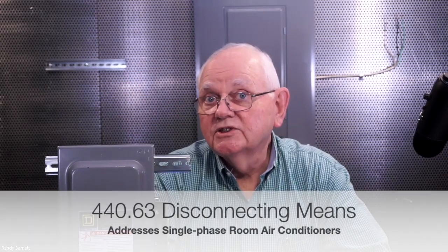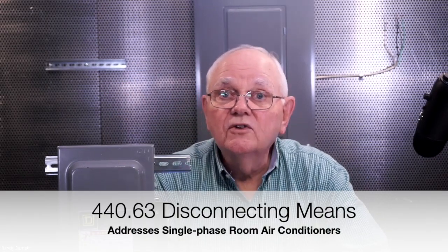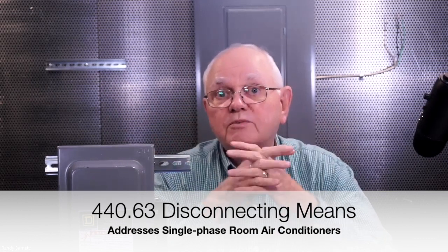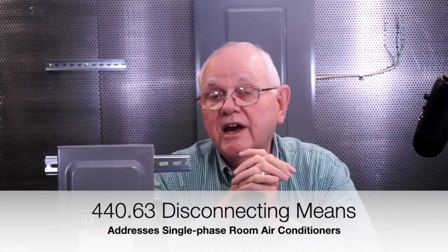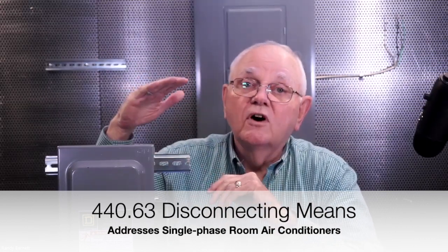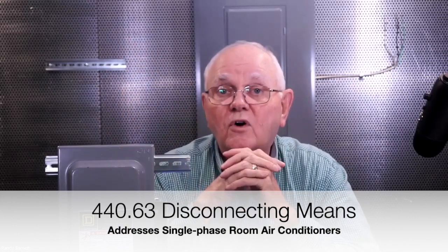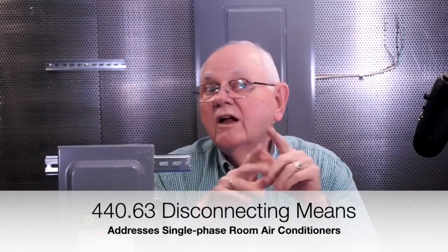In fact, there's a requirement in Article 440 for single phase room air conditioners. And it says that I can use that attachment plug as the disconnect, as long as the manual controls are no more than 6 feet above the floor for that air conditioning unit. Well, the very next section then tells you that the length of the power cord for that air conditioning unit can't be more than 6 feet anyway. So you're okay then, huh? So I have a disconnecting means.